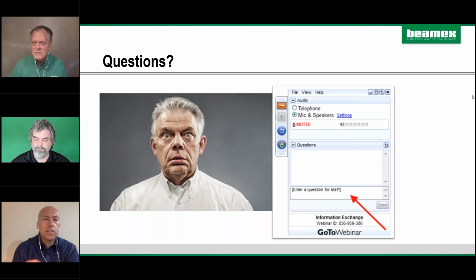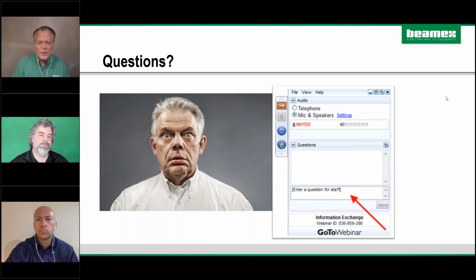The first question is, does the reference probe have to be immersed in a liquid medium, or can it be kept in the air? Well, you're going to put your reference probe in the media, whether it's the insert of a dry block, but if it's a bath, you're going to put it into the liquid so that it's measuring the temperature you're trying to set in the bath. So if it's a water bath or silicone oil, it belongs in there. If you have the reference probe up in the air, it's measuring the air temperature - like you saw here, it was 72 degrees in my office when we started the calibration, and that's what you're going to read wherever it is. I hope that answers the question.